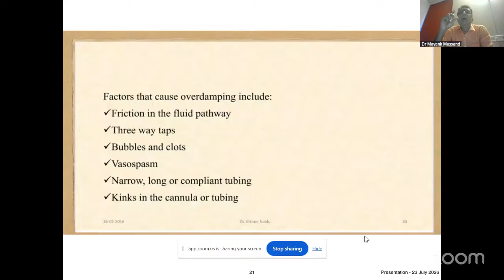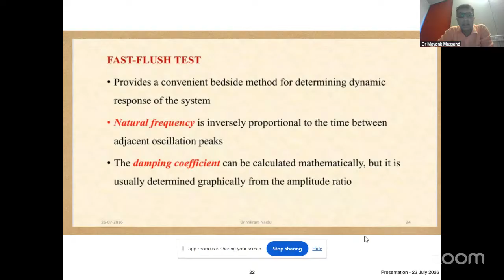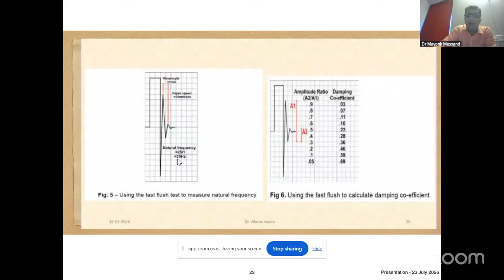Fast flush technique. Now, this fast flush technique is employed in order to activate the algorithm within the system. This is the most convenient process to determine the natural frequency as well as the damping coefficient. Okay. So, what is frequency? It is inversely proportional to the time. (Hindi: Take the inverse of the time between two waves, and that is the natural frequency.) Damping coefficient can be calculated mathematically, but it is usually determined graphically from the amplitude ratio. This is just for theoretical purpose. These algorithms are already loaded in our monitors, so they are automatically read. But I am just explaining it to you: between the two wavelengths, this is the frequency being calculated, and the damping coefficient is calculated accordingly.